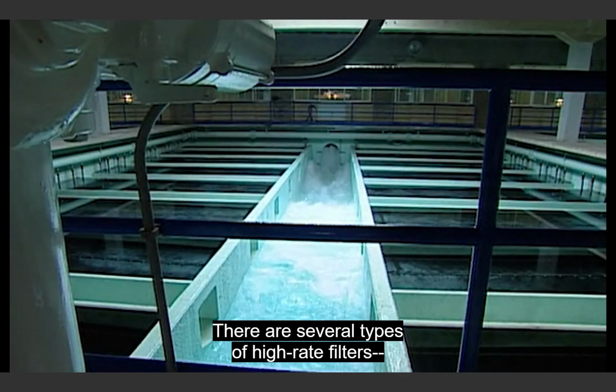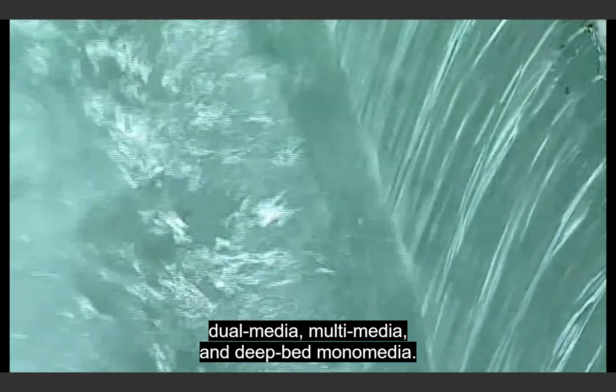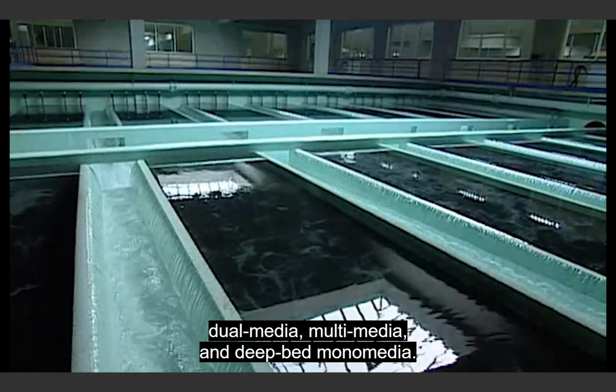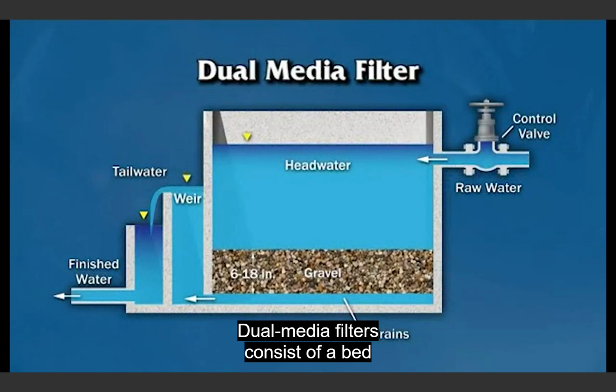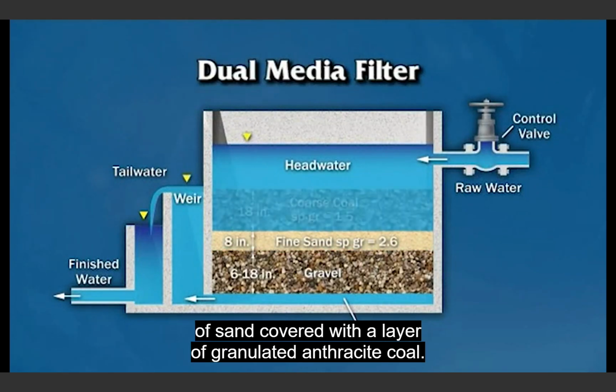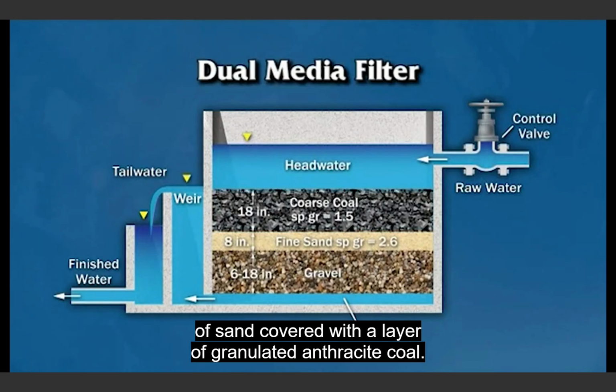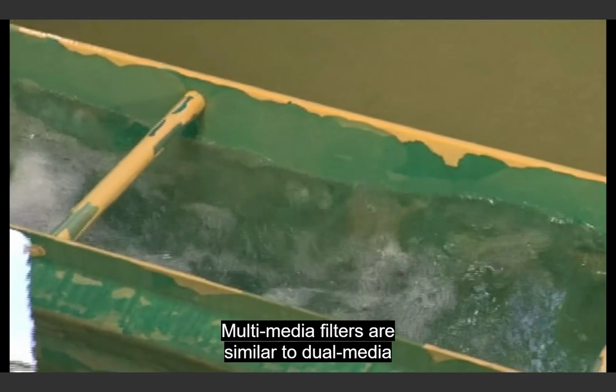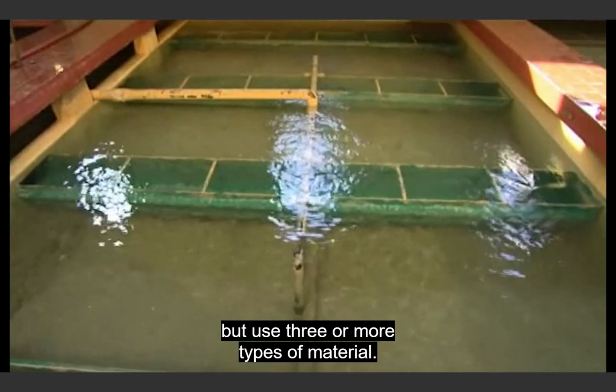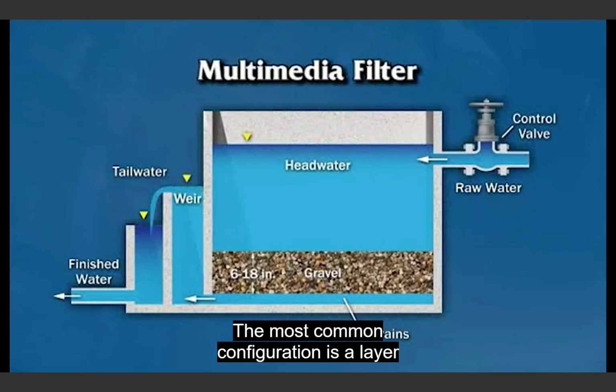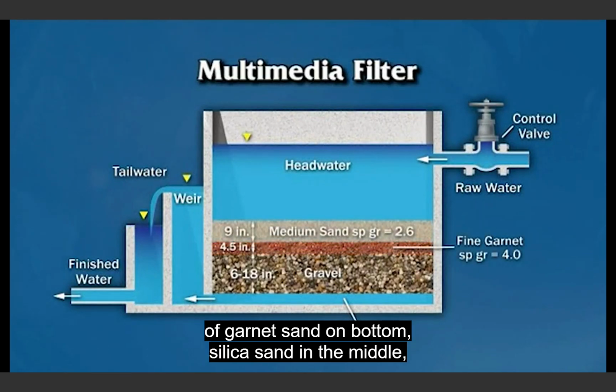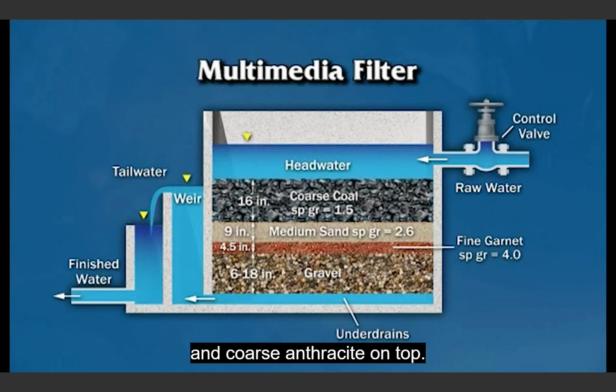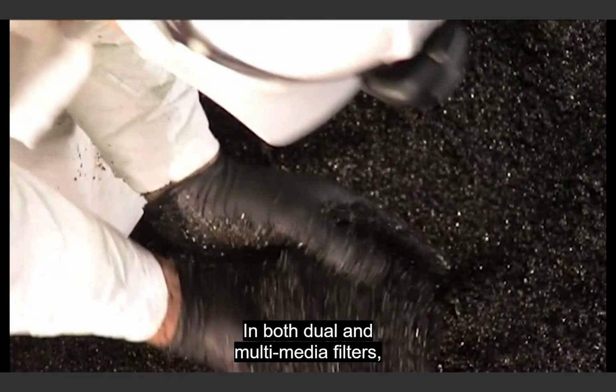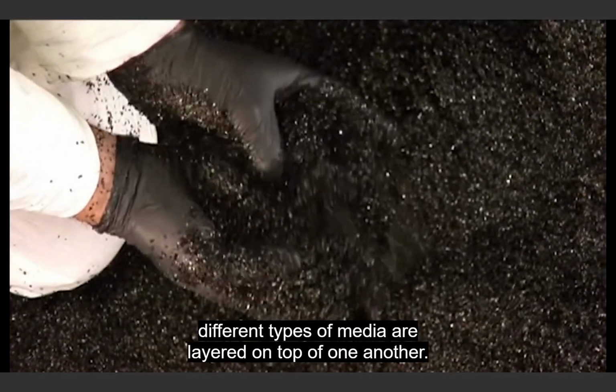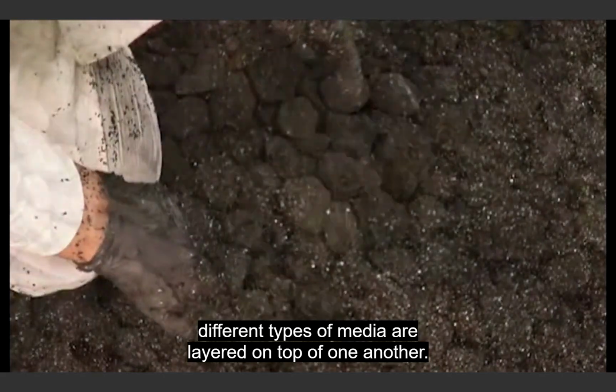There are several types of high-rate filters: dual media, multimedia, and deep bed monomedia. Dual media filters consist of a bed of sand covered with a layer of granulated anthracite coal. Multimedia filters are similar to dual media but use 3 or more types of material. The most common configuration is a layer of garnet sand on bottom, silica sand in the middle, and coarse anthracite on top. In both dual and multimedia filters, different types of media are layered on top of one another.